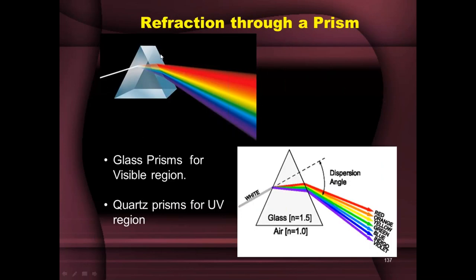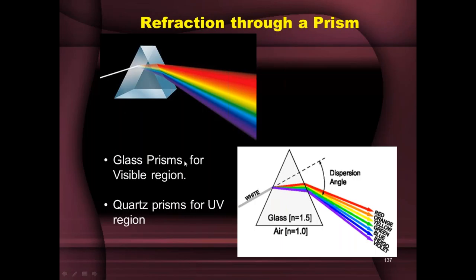Here you can see a pictorial representation. Shorter wavelengths are refracted more — you can see all the visible colors, with red being the longer wavelength showing less deviation, and shorter wavelengths showing more. You also see two refractions — one at the first surface and another at the second surface — which helps resolve different wavelengths in a prism. But longer wavelengths are not as well resolved as shorter ones. The prism must not absorb the radiation, so it should be made of a material transparent to the radiation being used. Glass prisms are used for the visible region, and quartz prisms for UV.